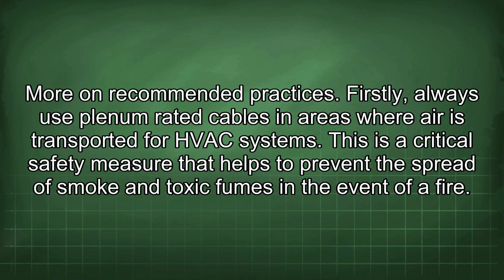More on recommended practices. Firstly, always use plenum-rated cables in areas where air is transported for HVAC systems. This is a critical safety measure that helps to prevent the spread of smoke and toxic fumes in the event of a fire.